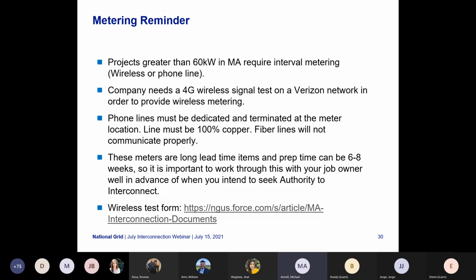Metering reminder. Projects greater than 60 kW in Mass will require interval metering. So that would be a wireless system or a phone line. We prefer the wireless meters versus a phone line. In those rare instances where you cannot get signal, we can use a copper wired system. Those will have to be dedicated and terminated at the meter location. The line must be 100% copper. Fiber lines will not communicate properly. So we do use Verizon on this. So when you submit your test, if possible, please use a 4G wireless signal test on the Verizon network with your form, so that we can verify that we will be able to communicate with that meter in that location.